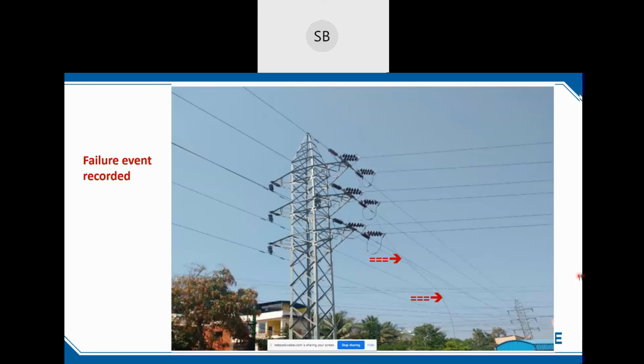This is our input 66 kV line, coming from BESCOM. I wanted to show how our energy management system is able to pinpoint failure data or failure analysis, such as the sudden inrush current during a failure and where it happened. Here you can see one of the conductors, the earth conductor on top, got disconnected from the tower and fell on the live conductor. This caused a dead short between the phase and the earth connectivity, and the power tripped completely. It took a lot of time because it was not on our side; the BESCOM people had to come and attend to the connections.